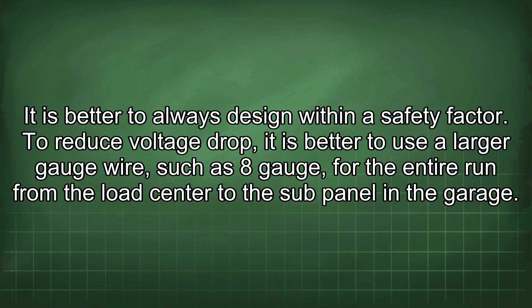To reduce voltage drop, it is better to use a larger gauge wire, such as 8 gauge, for the entire run from the load center to the sub-panel in the garage. This will ensure adequate voltage at the sub-panel in the garage and also account for future increases in load.